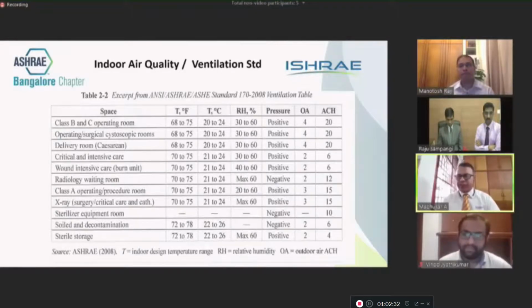Some operating theatres, for example, need a temperature of about 20 to 24 degrees centigrade, maintaining a relative humidity of 30 to 60%, with positive pressure, and you may need about 20 air changes with 4 outside air changes.